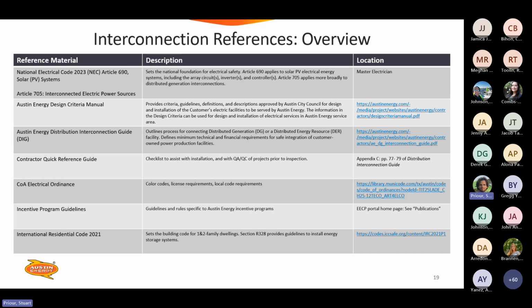We've got the Austin Energy Design Criteria Manual, of course, which is chock full of good information. I would say section 1.9 is of much relevance. It's the metering section that gives you lots of guidelines on what you'll need to do to interconnect and use proper meter equipment. We have the Austin Energy Distribution Interconnection Guide, which spells out in a little more detail what we require of PV systems and how they need to be designed. There are some good diagrams in there, as well as some interconnection documents having to do with how to interconnect our systems.